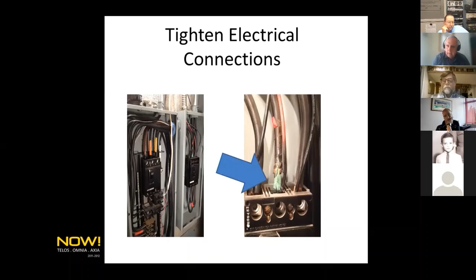It's important that you tighten electrical connections periodically. As you can see in this middle circuit here, the wires have actually burned because of the heat generated by a loose connection.